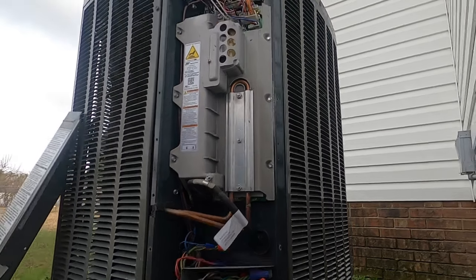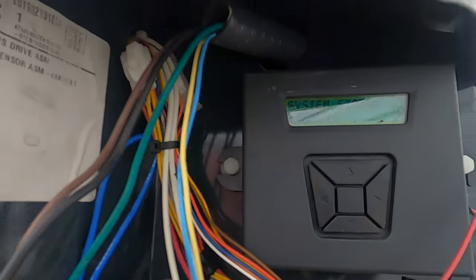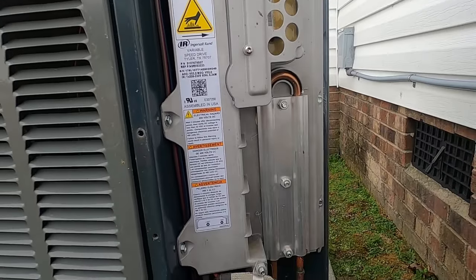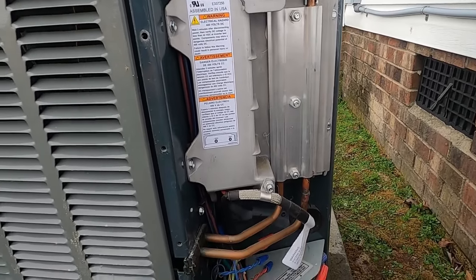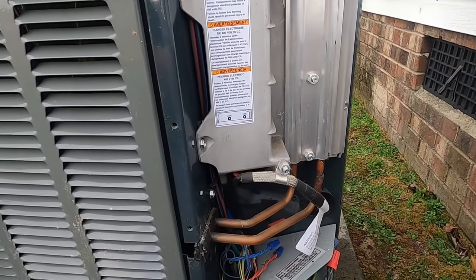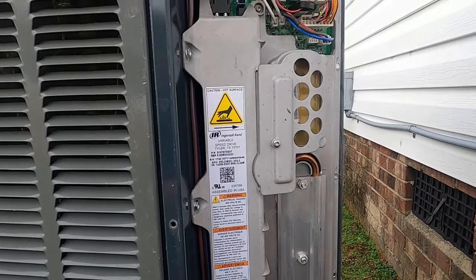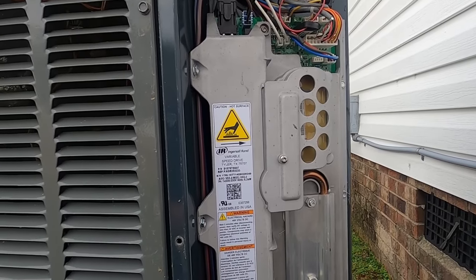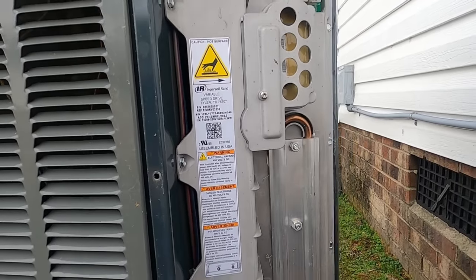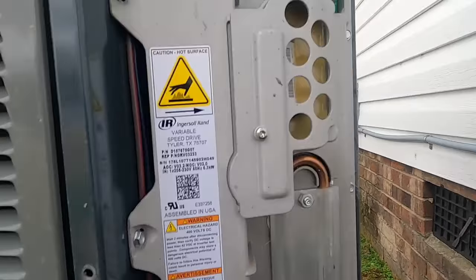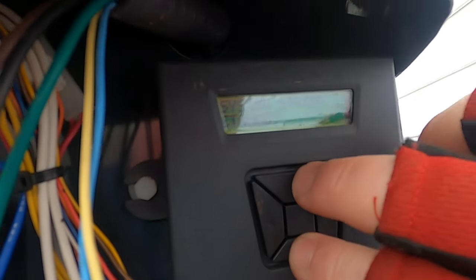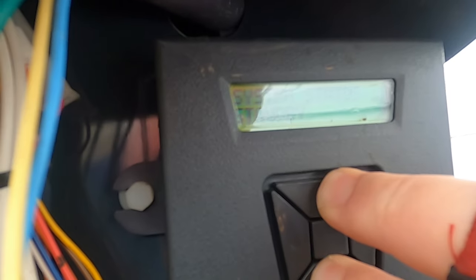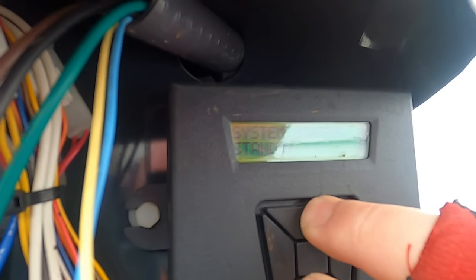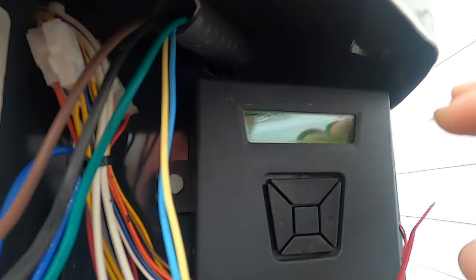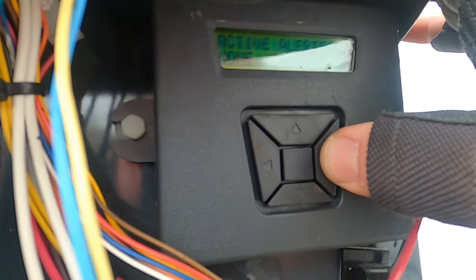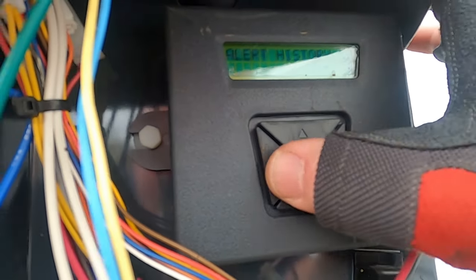But right now it's in standby. I've got the thermostat off on this, which is typically what I'll do when I first get to one. Just turn the thermostat off, and then we will go in and go through the history on the thermostat and then the outdoor unit. But it's in standby mode here, so I'm going to check my alerts real quick and see what it gives me here. They don't display the same as they do when you're checking on alert history.